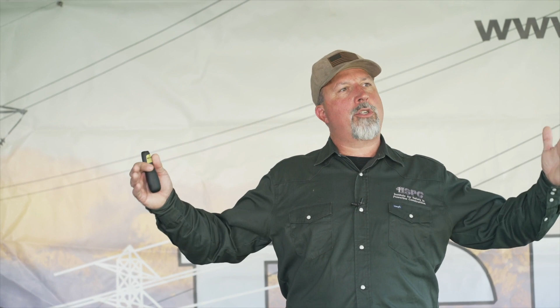And I've had too many people in the substation, including people that work for me, say to me, well, I'm working in a substation and I have half of it out of service and I have my sources of potential energy grounded, right? My high side coming in, my low side going out, I have those potential sources grounded. I'm good. No, you're not good. I'm here to tell you you're not good, right? Especially as we get up in the higher voltage substations where induced voltage comes into play, okay?